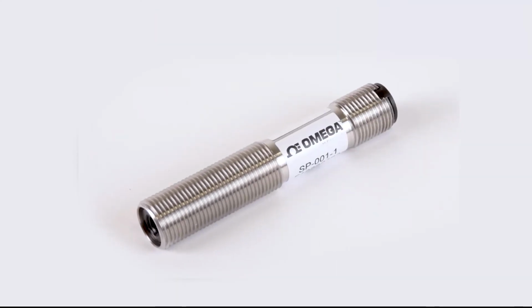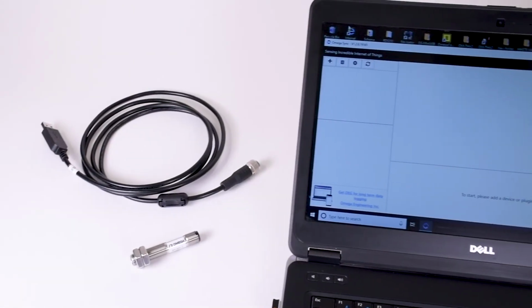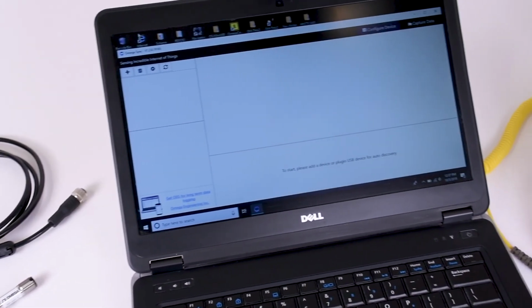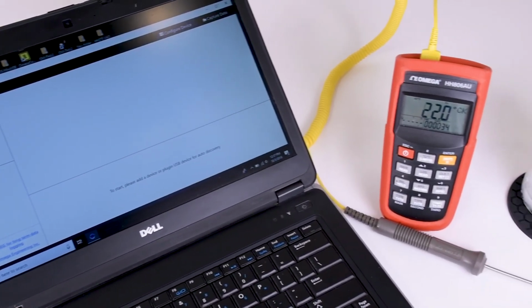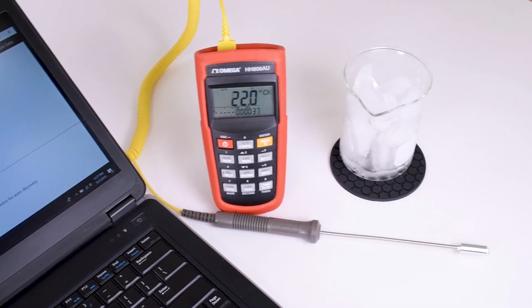To perform this configuration you'll need one smart sensor of course, and one smart interface cable, a Windows PC running Omega Sync software. Just to verify our reference temperature target, we're using a digital handheld thermometer with a thermocouple surface probe.